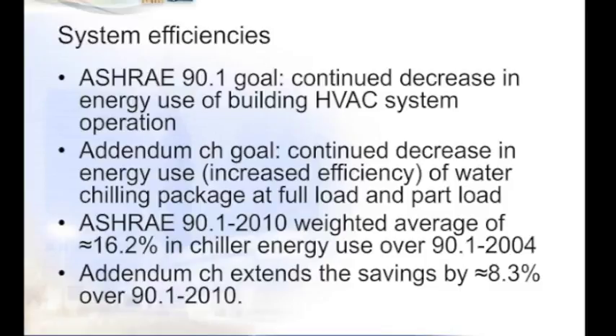ASHRAE 90.1 is all about efficiency, and one of the goals of the standard itself is a continued decrease in energy use of the building HVAC system. And the system is defined in 90.1 as the equipment, the distribution systems, and terminals that provide, either collectively or individually, the process of heating, ventilating, or air conditioning to a building or a portion of a building. This includes the chillers, which we're talking about today, along with fan energy and other forms of heating and cooling for the air or the spaces.